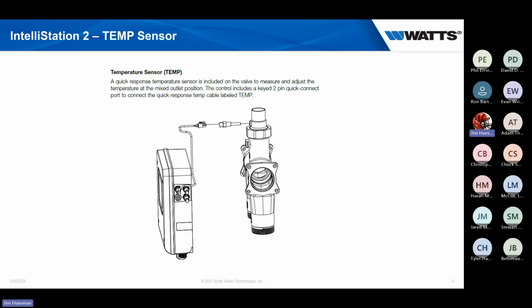As you can see, when we jump into this, we have our mixing valve and mixing chamber, and then our control box. Really, the only sensor you'll have if we're using this as just a single mixing valve, whether our old one or our new one, is just one sensor - our fast actuating sensor. As we're blending water, that water blends through our chamber, goes through the baffle to mix it, and then our sensor picks up exactly what that temperature is.